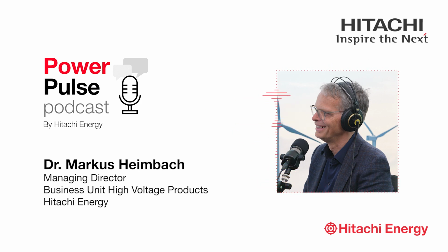And another topic is when you talk about an AC network, you can have circuit breakers. Because with 50 hertz, the current crosses the zero line 100 times in a second, and you are only able in an efficient and smart way to interrupt the current if you take it at the current zero. That's basically the principle why alternating current was winning the game in the past, because you can apply the transformer and use the circuit breaker as a main safety element.